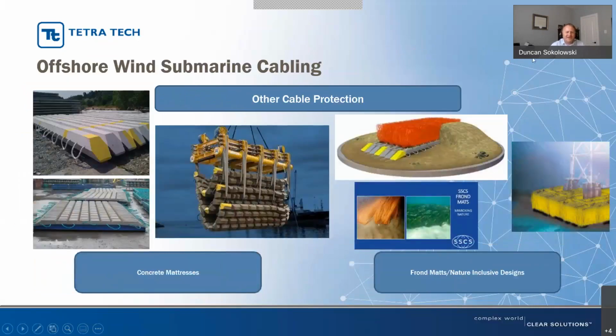Concrete mattresses on the left are fairly common, normally at cable crossings, where one cable crosses another and you need separation so they don't rub against each other. Normally there's a layer of concrete mats between the two: the top cable is laid over it, then another layer of mattresses is placed over the top. They normally have tapered edges so it's possible to fish over them, and they're positioned accurately so they lay alongside each other rather than stacked on top of each other. You try to bury the cable a bit, but at cable crossings it's difficult to get full burial, so mattresses are used at these locations both to protect the cable and to protect other users from the cable itself.